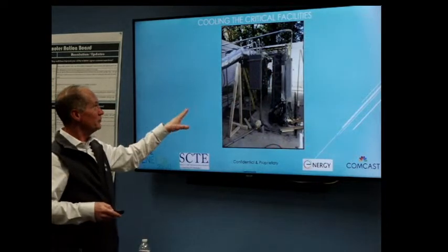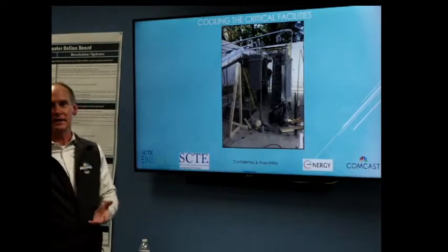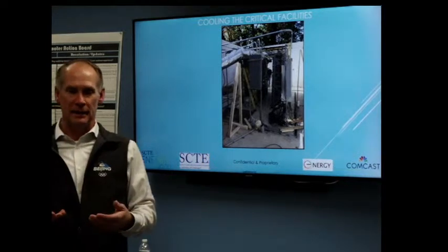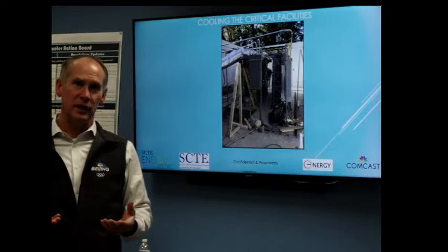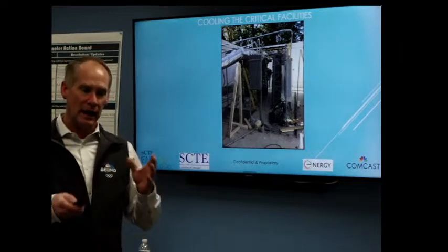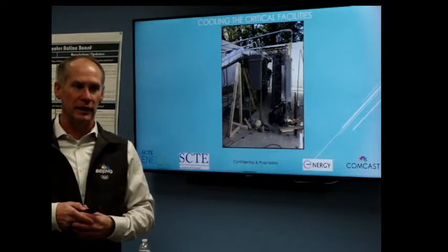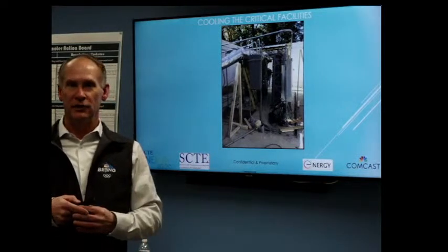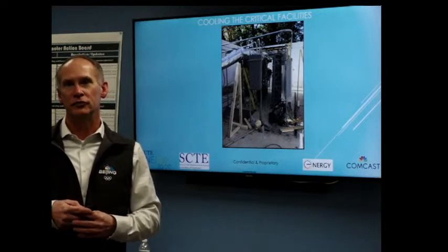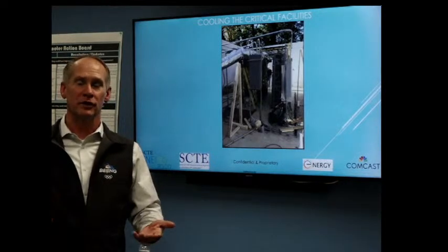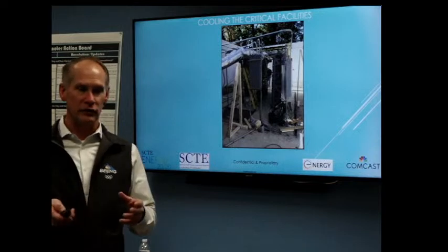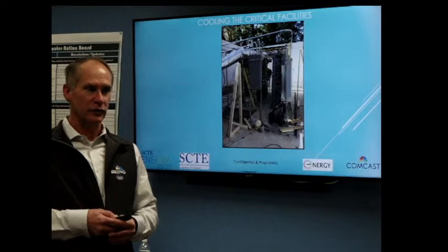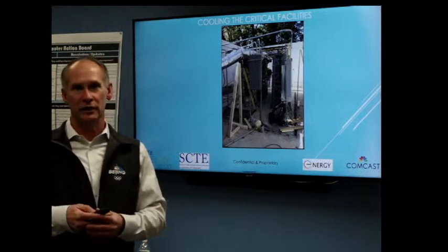And then we've seen this picture before. I put this here in jest, but this is ambient cooling. We're not really taking advantage as much as we can of ambient cooling. Again, I'll talk through the work at the P&E lab in Downingtown. They're great at trying to figure out the correct temperature that equipment should be operating at. We as critical infrastructure engineers and operators need to understand that if the equipment can operate at a higher temperature, let's utilize free cooling a little bit more.